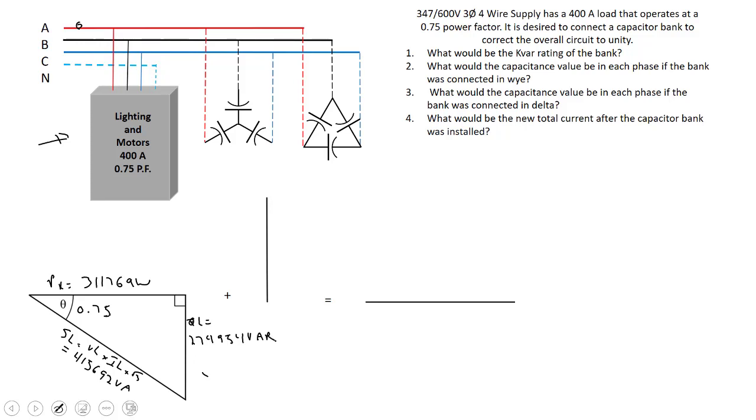Because this is corrected to unity, all that really means is the only thing that's going to be left coming from the circuit is going to be the power, the true power of our loads. The S total, final S total, is going to be exactly the same as the P total. In this case we just have these loads here, so that would be 311,769 VA or watts because it's exactly the same value.